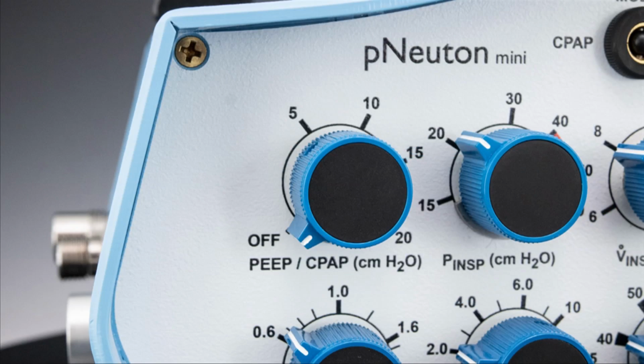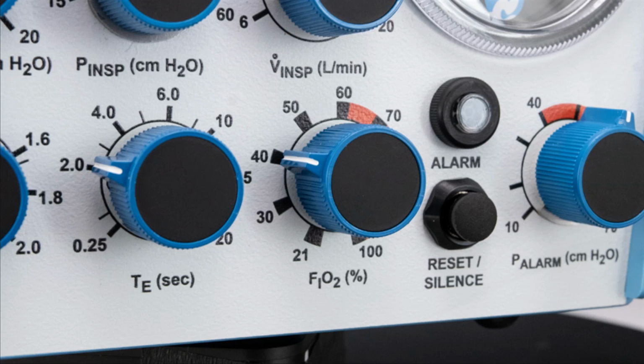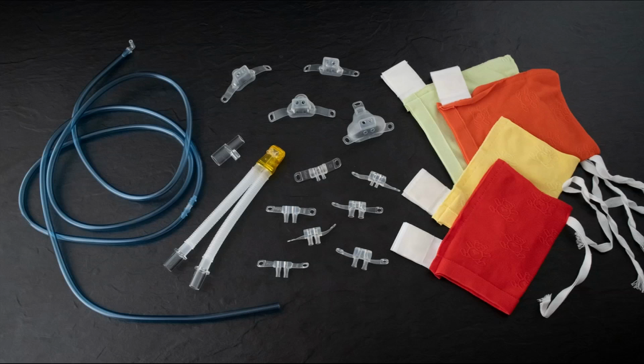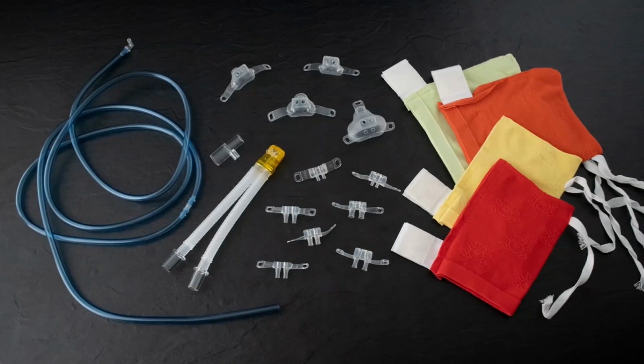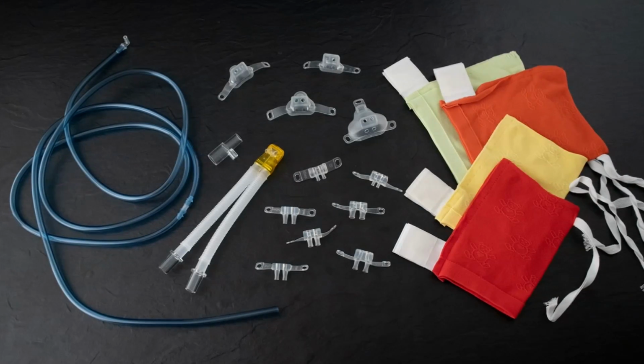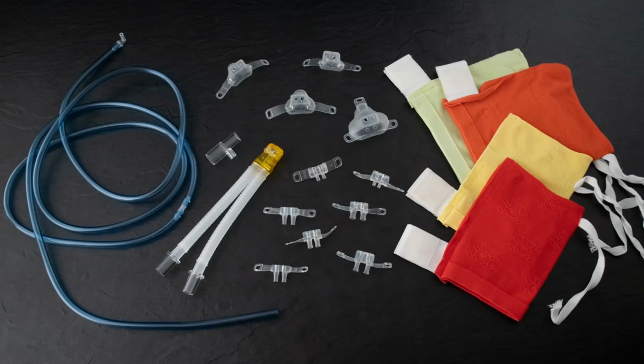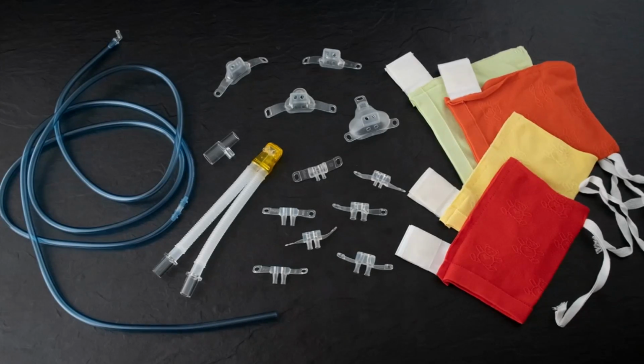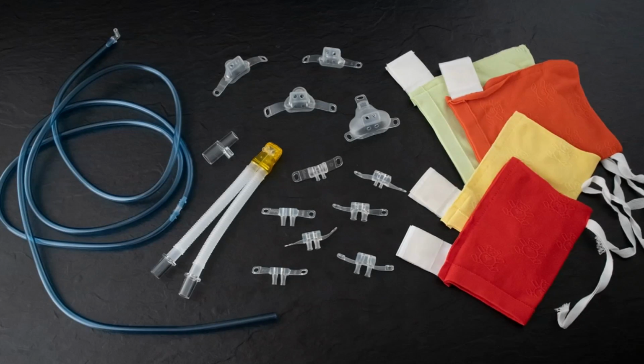The PEEP CPAP control has a calibrated range from 0 to 20 centimeters of water and has automatic sensitivity for changing patient needs. The oxygen concentration is maintained at the set percent on the oxygen control FiO2. As you will see while using the Mini, the PEEP CPAP system is very responsive and supports the non-invasive application of CPAP with a complete range of nasal prongs and masks.